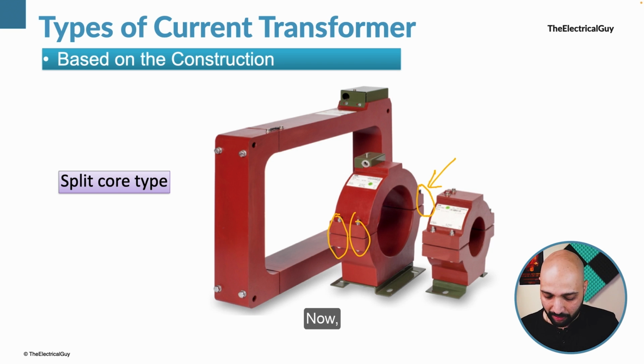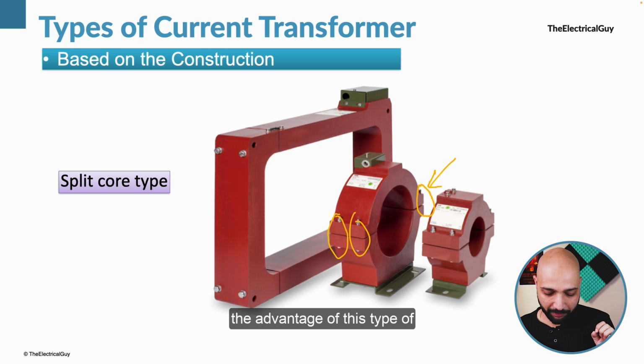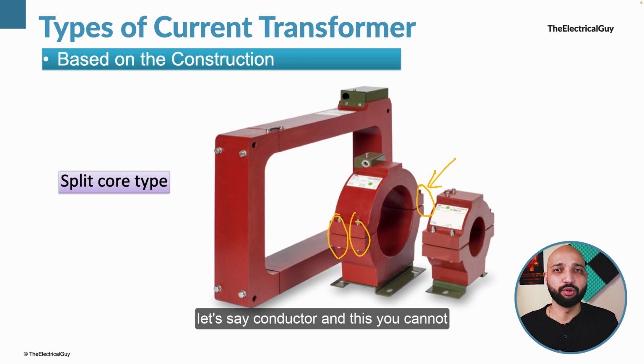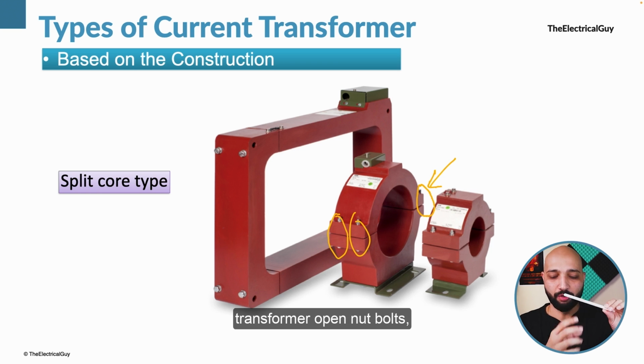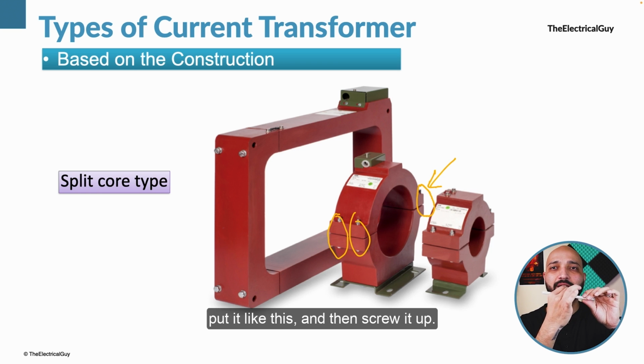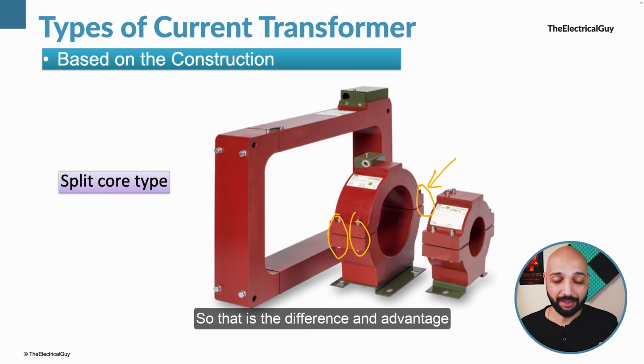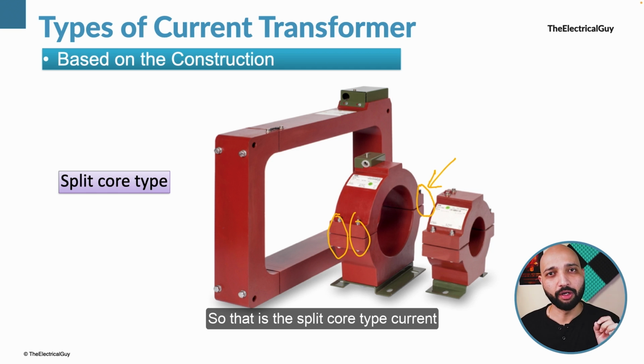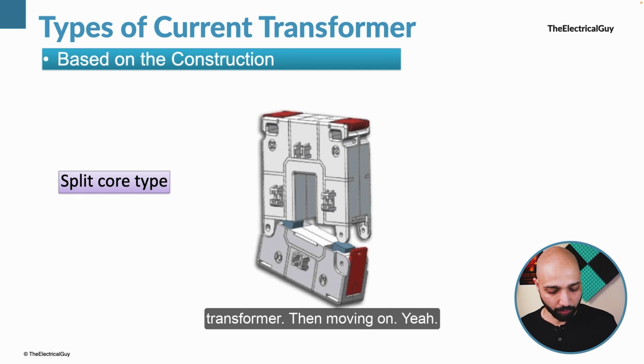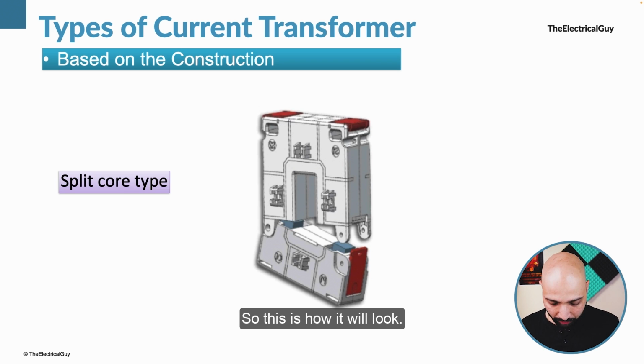Now the advantage of this type of current transformer is that, let's say you have a conductor that you cannot remove, right? In that case, you can get this split type current transformer, open the nut bolts, put it like this, and then screw it up, right? So that is the difference and advantage when we compare it with the regular window type current transformer. Right, so that is the split core type current transformer. This is how it will look. It will open from this side and then you can place it on the conductor like this, right?